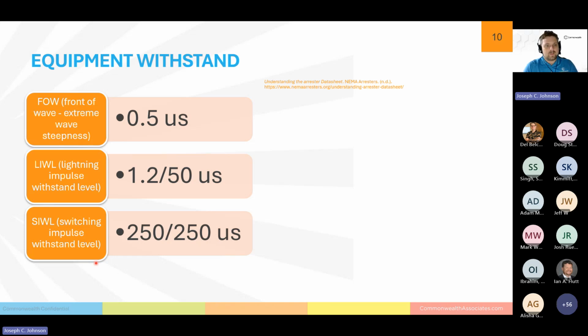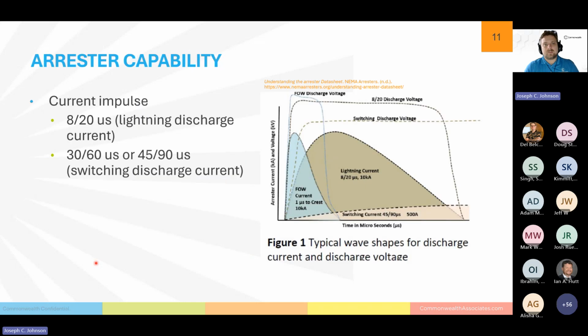This is microseconds. And then you have the switching impulse withstand level for switching events. As you can see, that is significantly slower compared to the other two events. So if you imagine the amount of energy that's in that wave, imagine the integral of the area underneath is really the power that's being delivered. So that's why these switching impulses can be very significant, because they're much longer duration and have a lot of energy behind them. As a note, these are for the equipment themselves, for things like transformers, buses, breakers, and these are the waves for arrester capabilities. So there's a current impulse test used for arresters, and that is an 8 microsecond time to crest for lightning, and a 30 or 45 microsecond time to crest for switching.